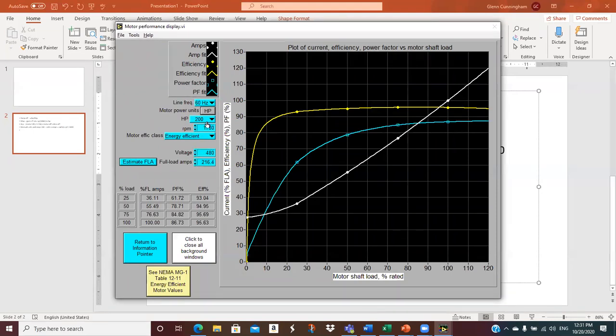So right now I'm sitting on a 200 horsepower motor. If that thing was 50% loaded, if it was putting out 100 horsepower, then this is my percent full load amps. At 50%, my percent full load amps is 55.49, which is right here. My power factor is 78.71, which is here. And my efficiency is 94.95, which is here. So this is great. I use this probably more than I use PSAT.